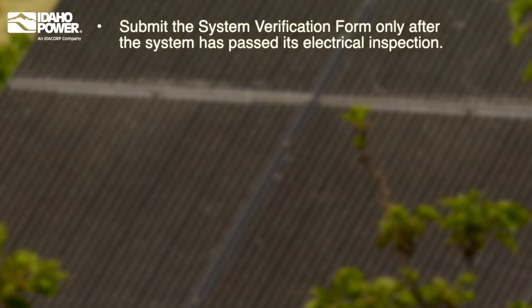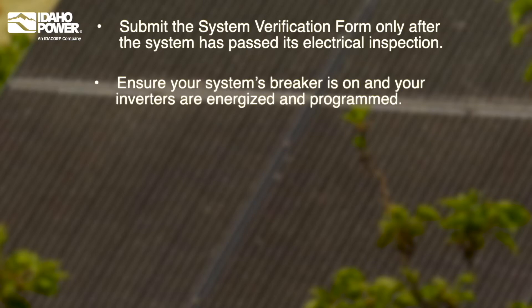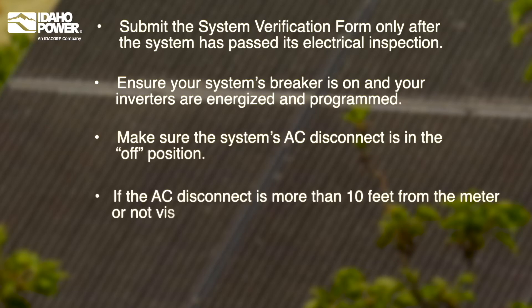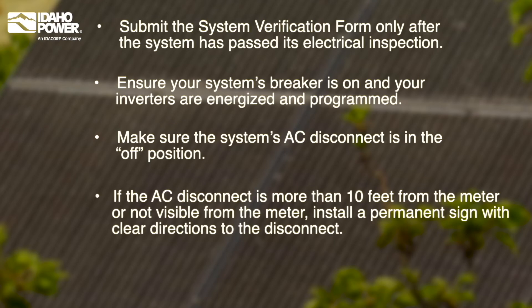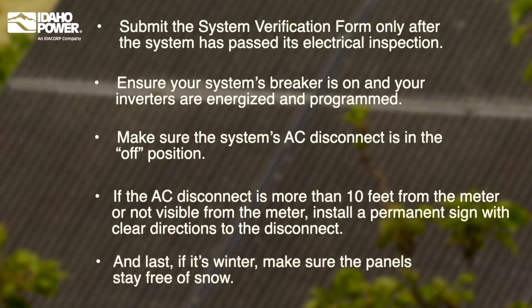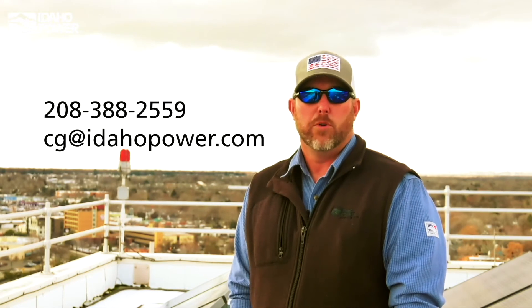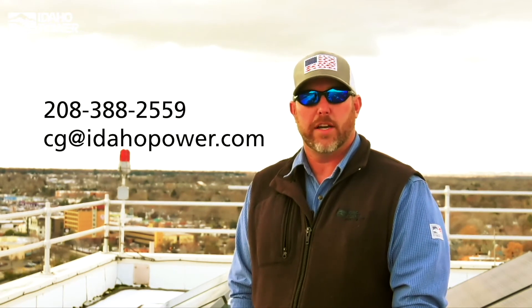To help ensure your system is ready for the inspection and the meter change, remember these tips: Submit the system verification form only after the system has passed its electrical inspection. Ensure your system's breaker is on and your inverters are energized and programmed. Make sure the system's AC disconnect is in the off position. If the AC disconnect is more than 10 feet from the meter or not visible from the meter, install a permanent sign with clear directions to the disconnect. And last, if it's winter, make sure the panels stay free of snow. Any questions, please contact Customer Generation at 208-388-2559 or email us at cg@idahopower.com.